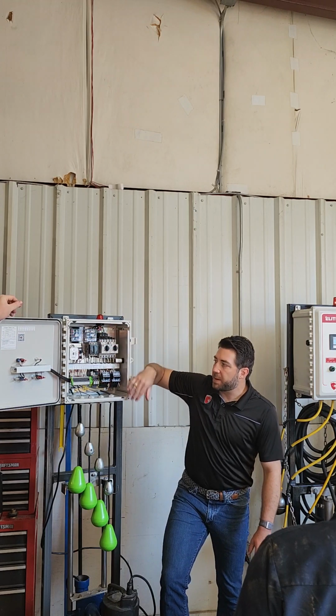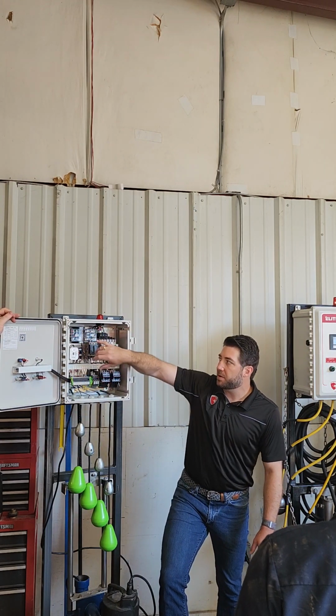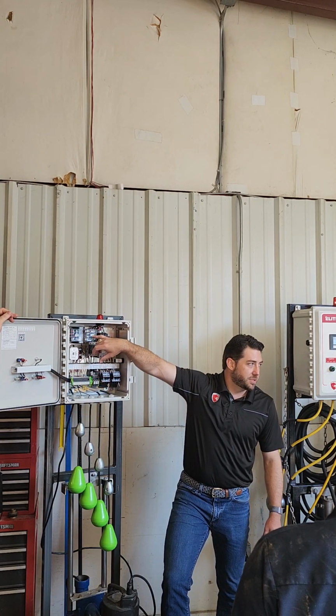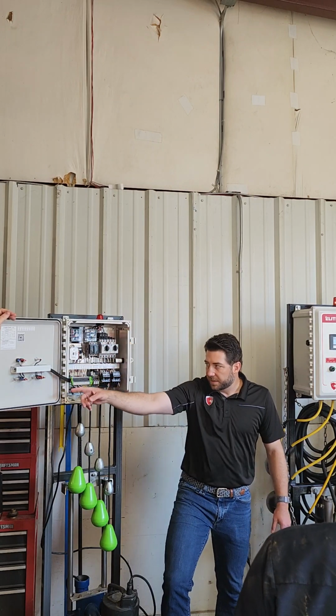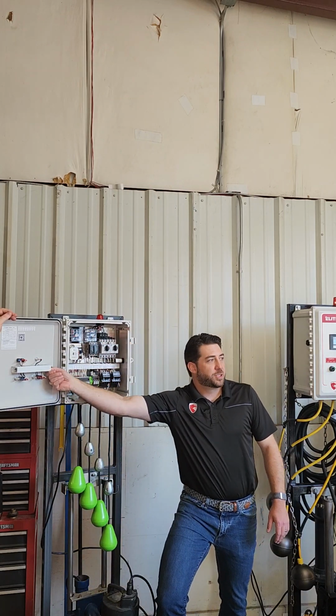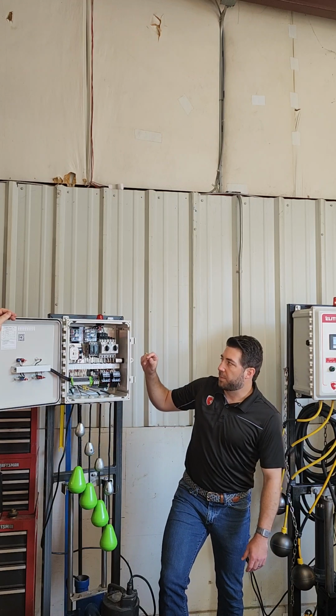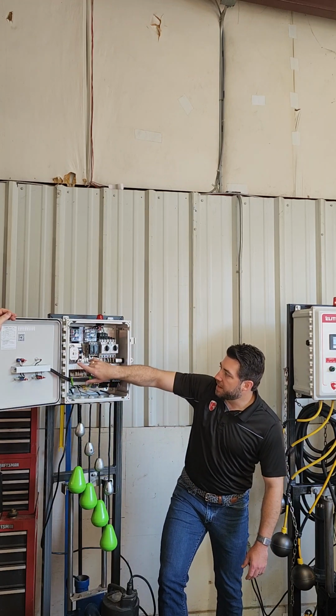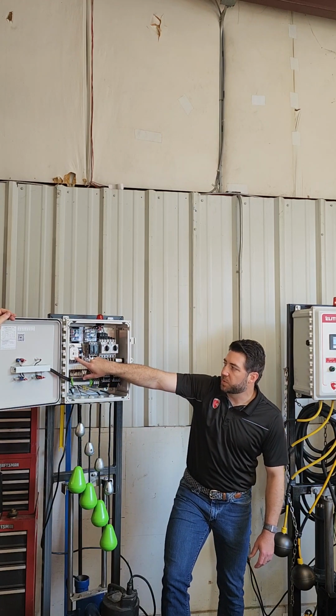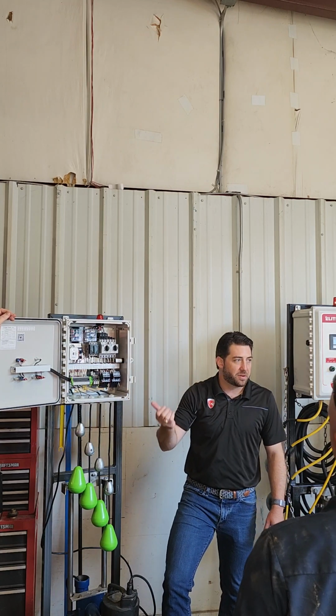Okay. So there would normally be fuses behind the plastic. If you have power coming in but you don't have control power, checking those fuses is a good place to start. This is not a good demo panel, because usually we have spare fuses hanging there so you can replace those. Underneath that we've got our alternating relay. This is what's going to switch the pumps every time we go through the sequence.